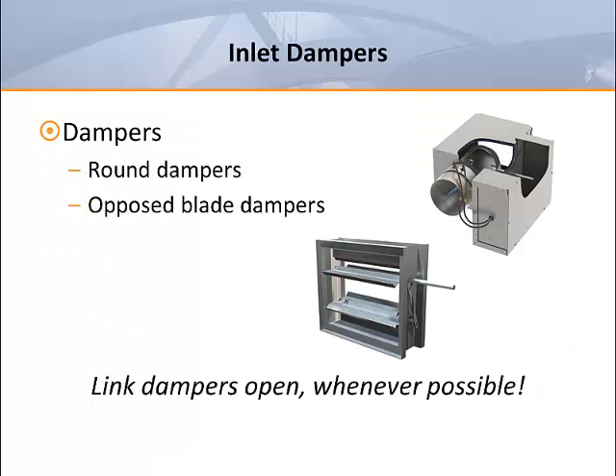Most terminal units use dampers to regulate primary air flow. The two common types of dampers found in terminal units are round or rectangular. Rectangular dampers can be single-blade or multi-blade. Multi-blade dampers are sometimes built with opposed blades. They are all suitable for use on terminal units, but round dampers have the advantage of lower cost, lower leakage, and simplicity. Multi-blade dampers tend to have higher cost, higher leakage, and more moving parts. Some people tout the linear response of the opposed blade damper as a control advantage, but that really hasn't been true since pneumatic controls were largely replaced by digital controls.